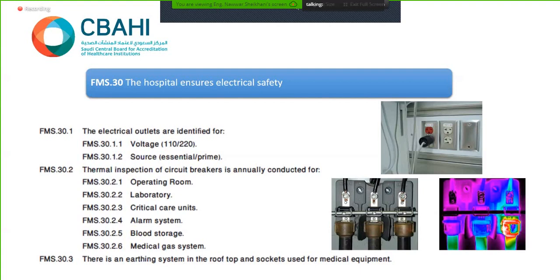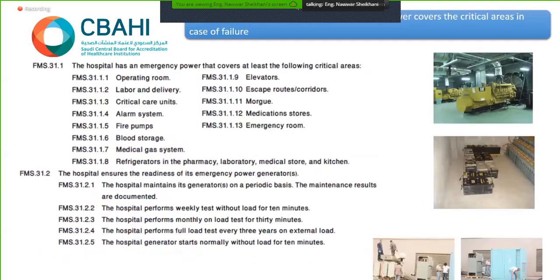Then they put a metallic bar around 10 meters outside the hospital and measure the resistance. I think the maximum should be 0.5 ohm. The hospital has emergency power. Cover the following. Of course, here we check the single line diagram to make sure that these locations are really connected to the generators, starting from operating theater, labor and delivery, critical care unit, fire pumps, medical gas system, morgue, emergency room, elevators, escape routes and corridors. All this will be connected.